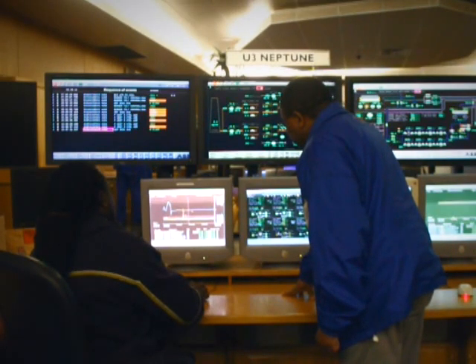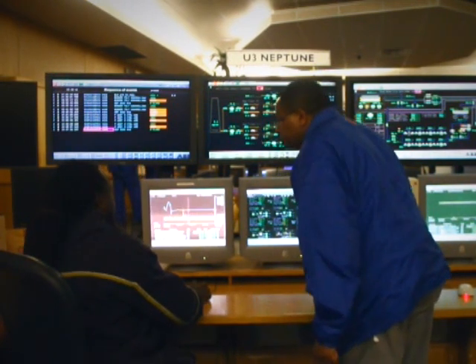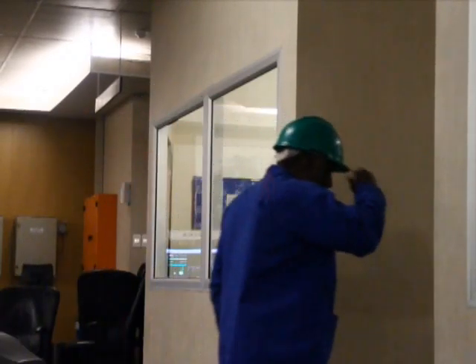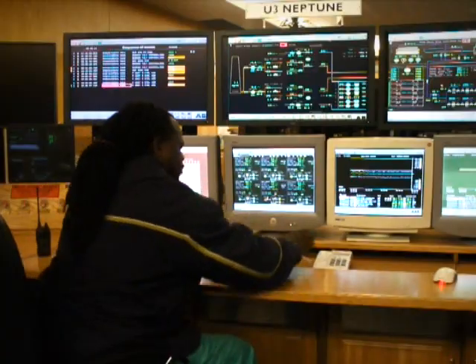Operators have been trained to respond to this alarm by carrying out a series of cross-checks with other instrumentation to see if there are any other signs of a leak. An operator is also sent to the boiler to look and listen for any telltale signs. If a boiler tube leak is confirmed, a decision to shut the unit down is given by the responsible person on site following discussion with system operations and the divisional executive generation.